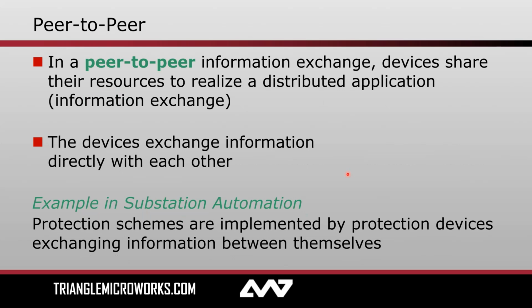To contrast client and server, there's another paradigm for devices that are communicating with each other, and this is peer-to-peer. Whereas in client server there's an inherent hierarchy, in peer-to-peer everyone exists on the same plane and they're just sharing data between each other. An example of this, bringing it back to a substation, would be those IEDs down at the bottom, those servers, which are all able to share GOOSE and sample value messages between them. For example, one IED might detect a fault and issue a trip signal to another device that's actually responsible for opening the breaker. These two devices are just peers to one another.